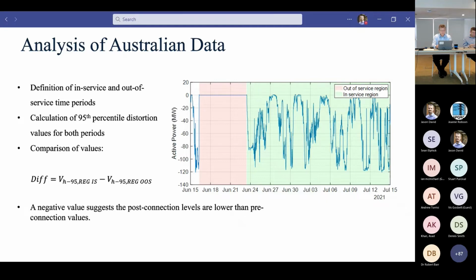And ultimately we would define a 95th percentile value for an out-of-service time period, and a 95th percentile value for an in-service period, as you can kind of see in the graph there. Using a simple equation of in-service minus out-of-service values, we assess an estimated impact or change in harmonic voltage distortion during the connection of the installation itself. A negative value or result will ultimately suggest that post-connection levels are actually lower than pre-connection levels.